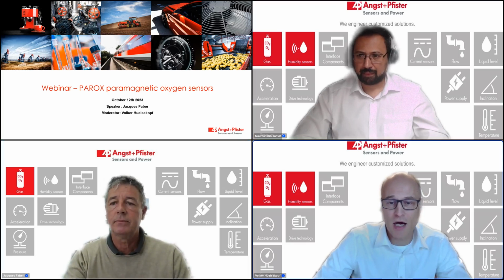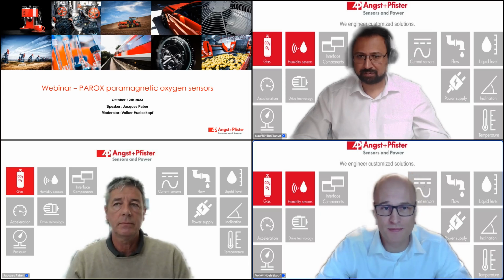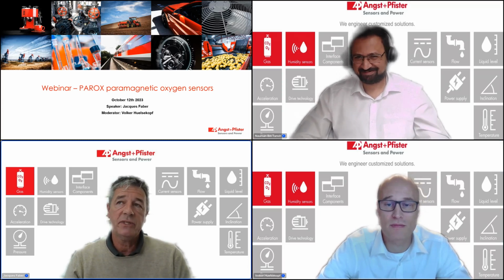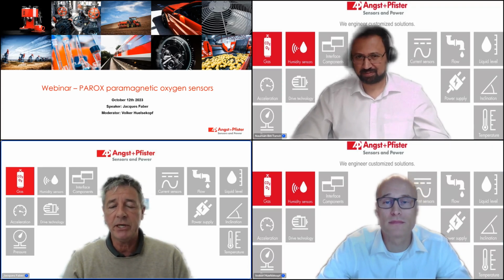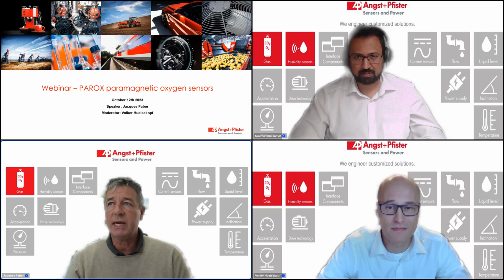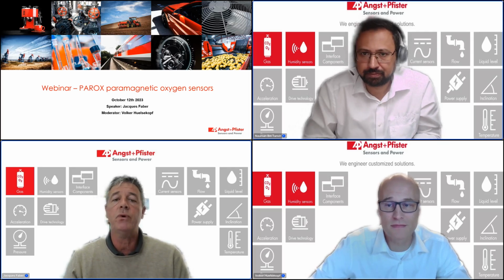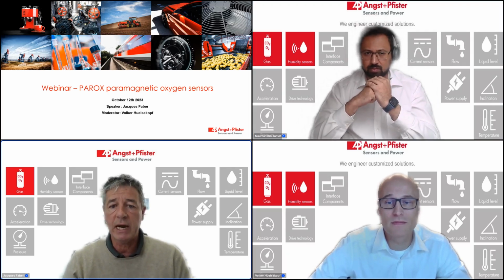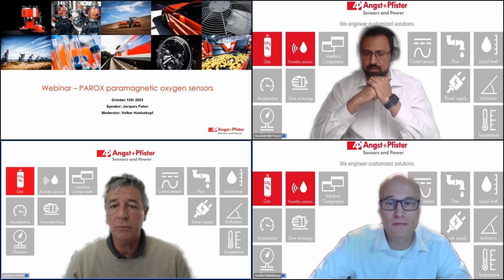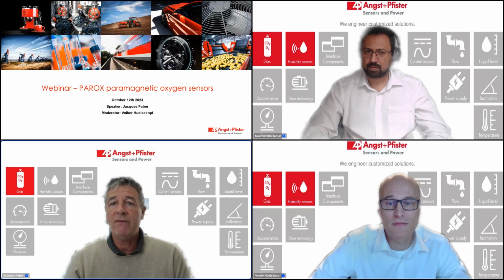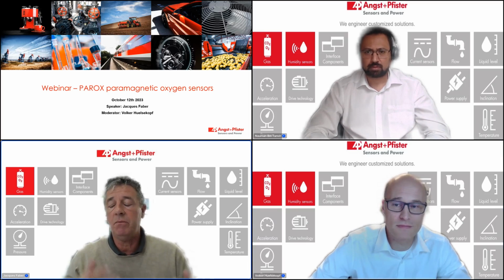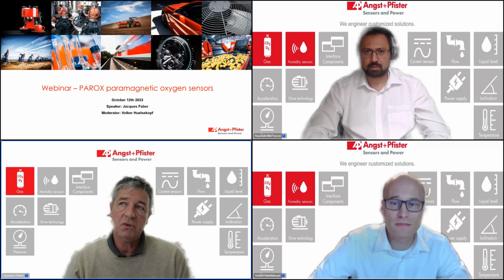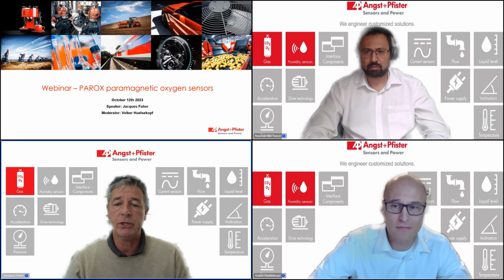Okay, thanks. And how often do we recommend a 0-point calibration? That's what I tried to say in the presentation. It very much depends on the application that you have. If you have a very precise application, it definitely makes sense to do a quick calibration before you start measuring. It takes 2-3 minutes. If you have a constantly running application, it makes sense to calibrate maybe every week or every month. But it really depends very much on the application that you have. So there is no one answer to this question.